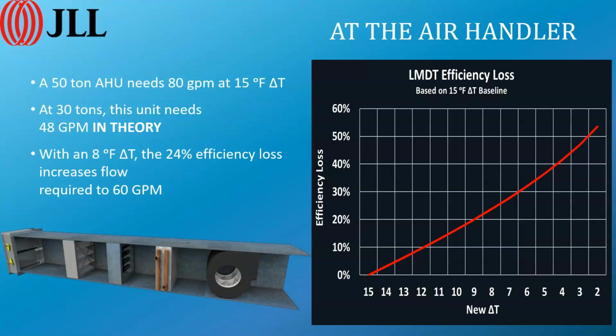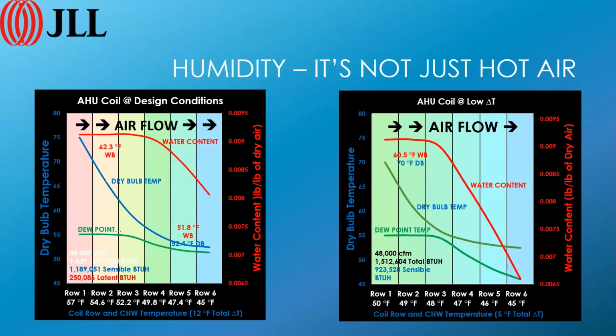At the air handler, we have an issue with log mean temperature difference that we want to pay attention to, and this is one of the things that's kind of important. A cooling coil is a heat exchanger, and if the design is a 15-degree delta T, like in this case, a 50-ton air handler needs about 80 GPM. At 30 tons, in theory, it's supposed to be 48 GPM, but because the efficiency loss occurs at a lower delta T, you actually need more water than that. You need 24% more, an additional 12 GPM, because of the change in efficiency of the heat exchanger. Now, there's another thing that happens that is a real bummer. The coil on the left, airflow is going from left to right.